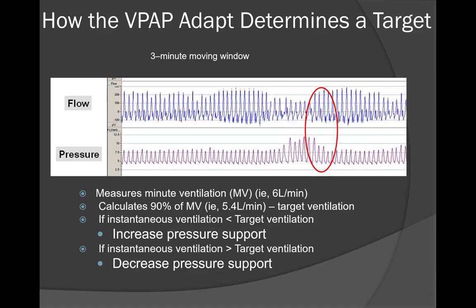How do you think it can overventilate the patient? If you have a leak, right? Not leak, you go to the bathroom. No, the leak in the mask. Unintentional leak. When you have an automatic adjusting device and you have leak, the leak triggers the device to increase pressure.